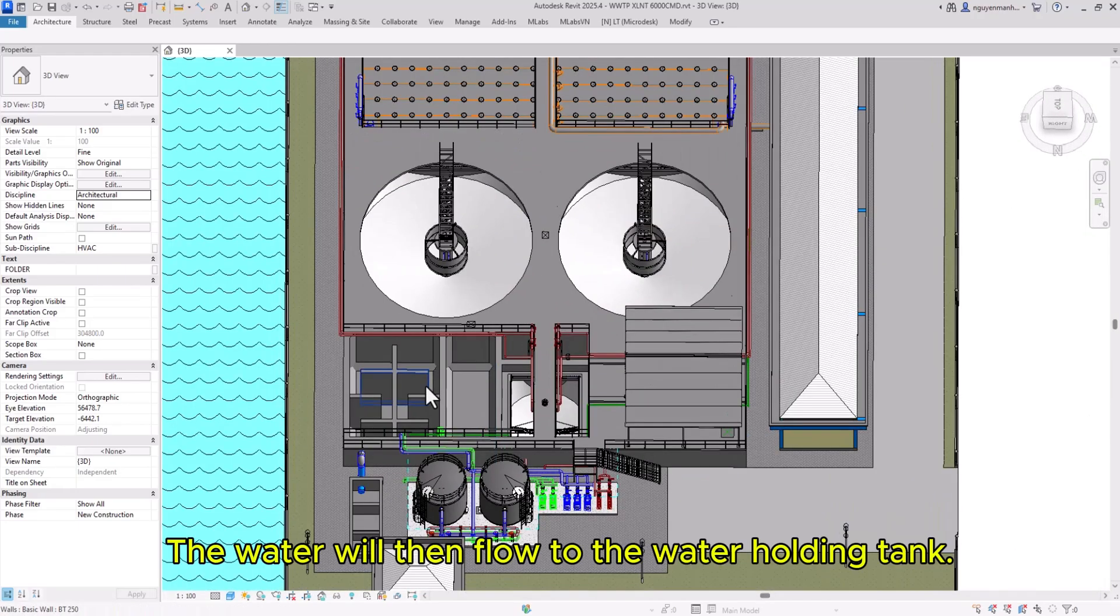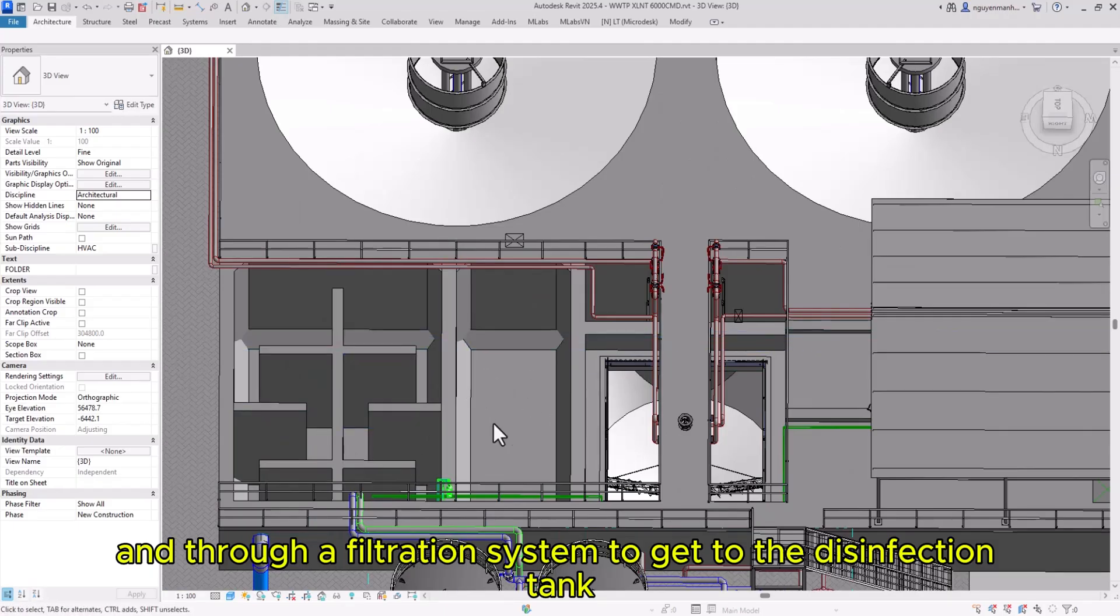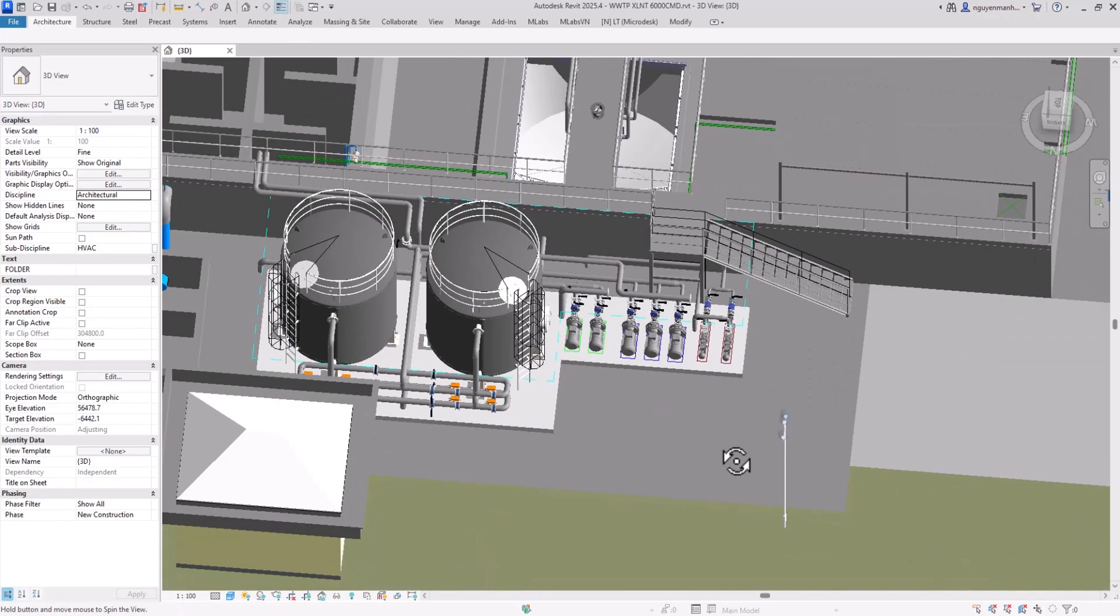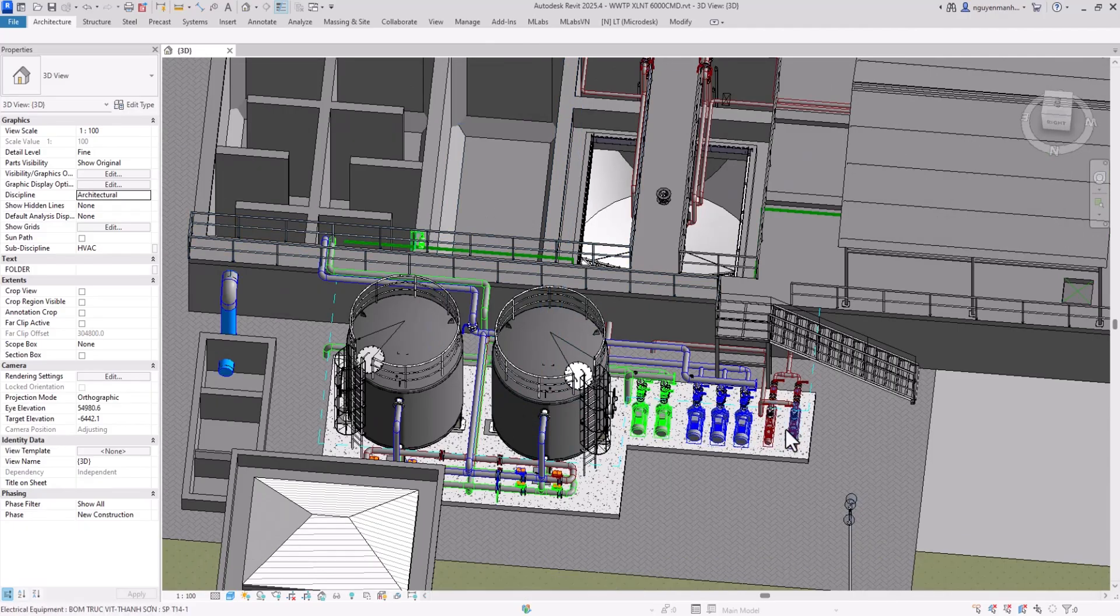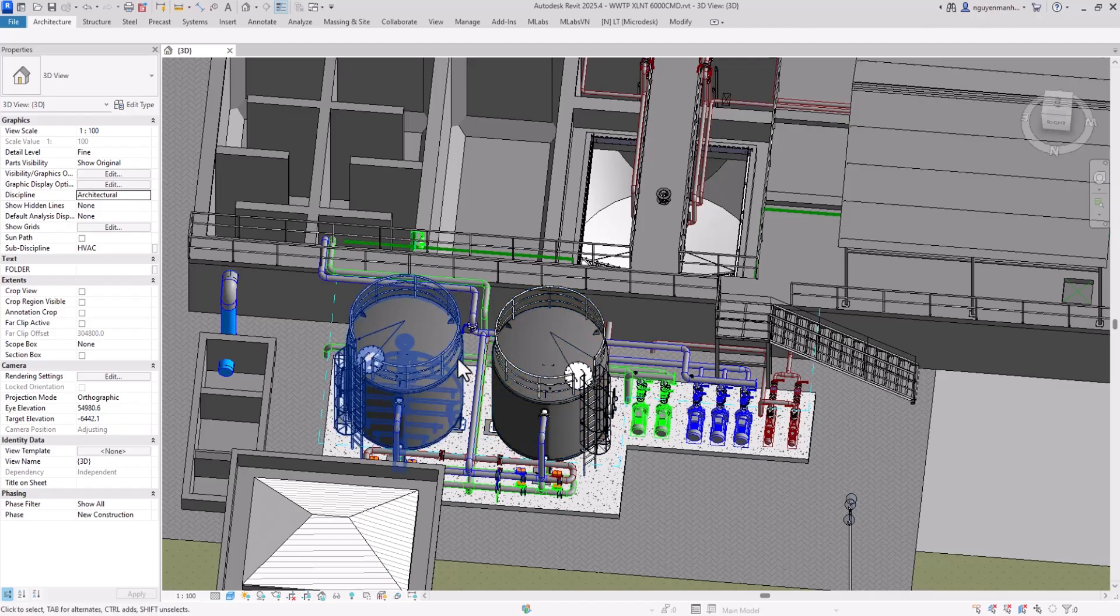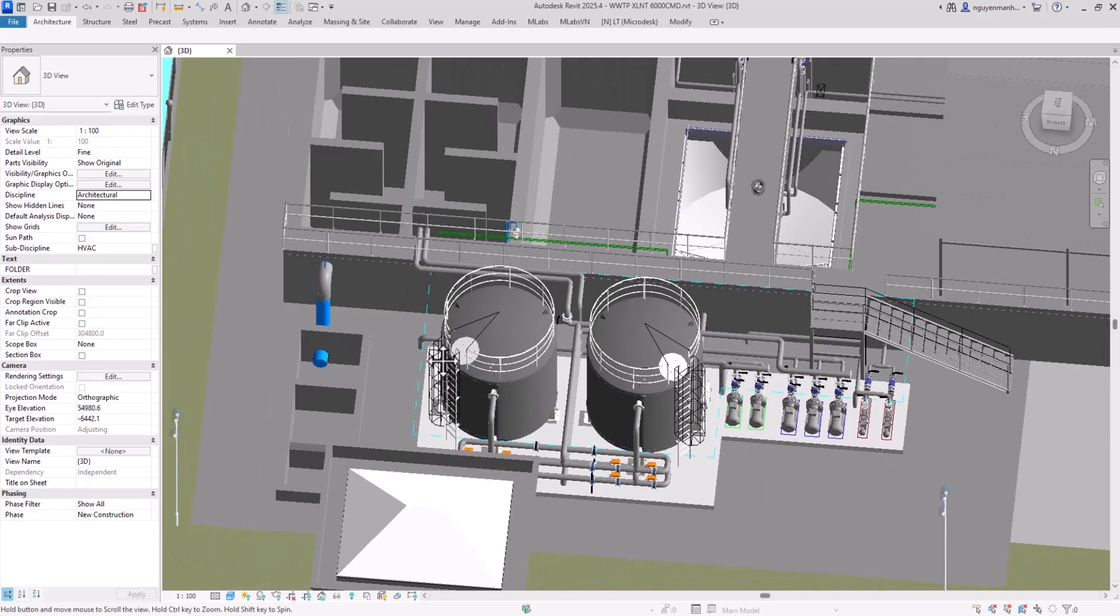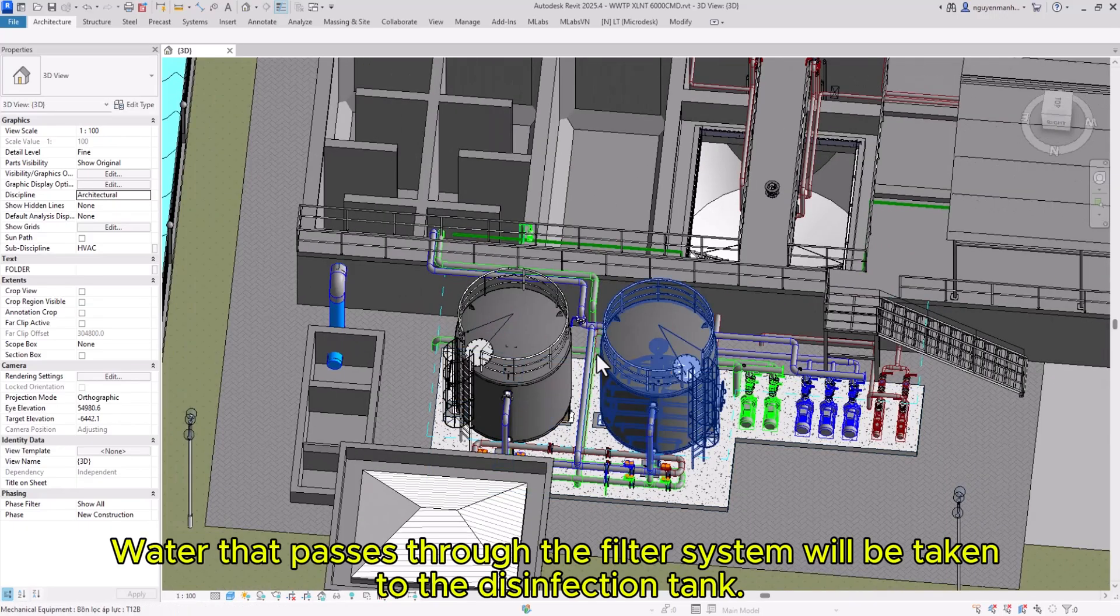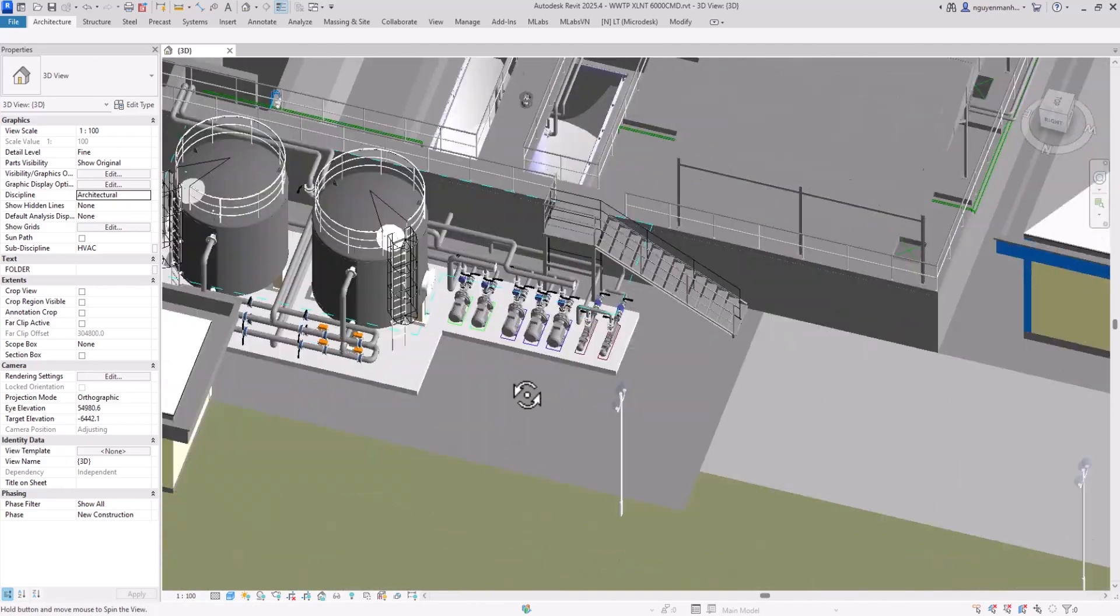The water flows to the water holding tank and through a filtration system to reach the disinfection tank. The filtration system uses sand filters and activated carbon, with filter pumps, sludge pumps, and backwash pumps. This is a sand filter.